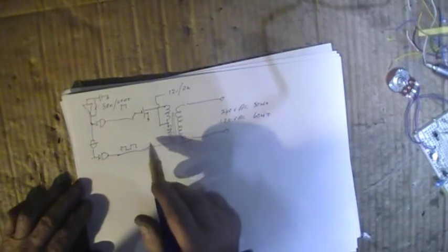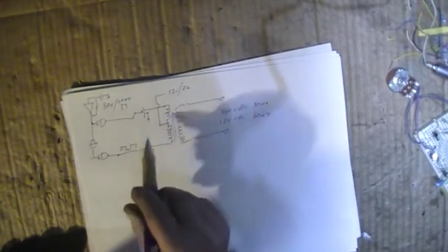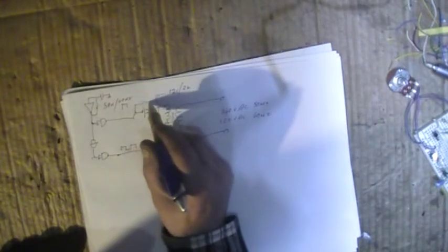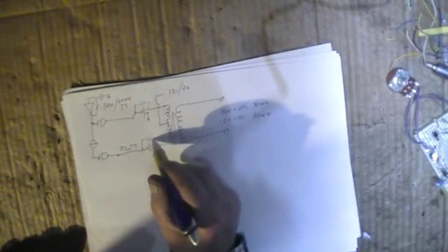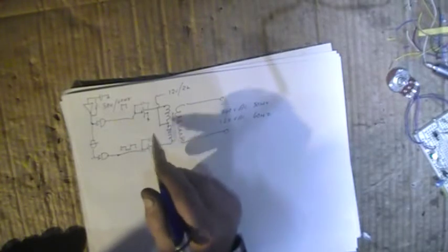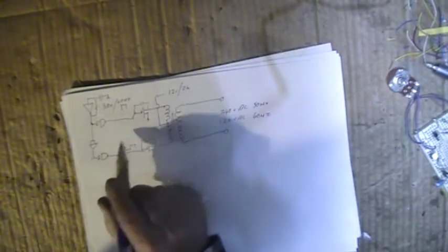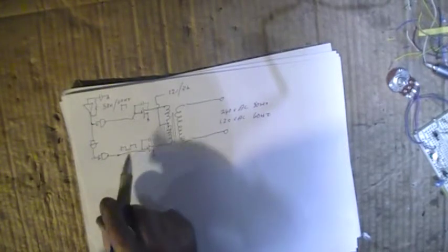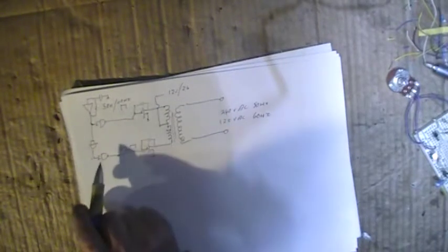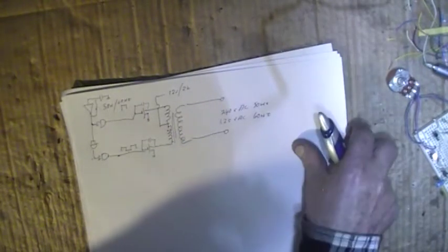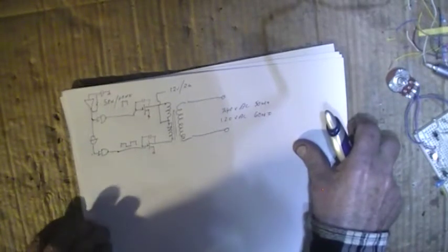The other good thing with low frequency inverters is that the amount of capacitance in the FETs is amplified by the frequency. The higher you push frequency, the worse this Miller capacitance gets. At 50 cycles it's still there, we can use upwards of half an amp to an amp just to turn one FET on and off very quickly. We still have to turn them on quickly with this, but because the commutation time is now just a very small part of the total conduction time, it's not as critical as it was in the high frequency design.